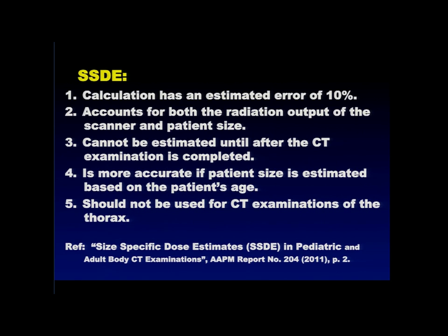Number 2, it accounts for both the radiation output of the scanner and the patient size. If the patient size changes, SSDE will change, even if the technique factors are unchanged. If the patient size doesn't change, but the technique factor is changed, CTDI vol will change and SSDE will change. Okay, so it accounts for both.